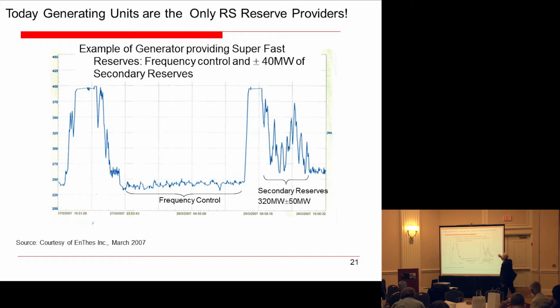Look at this generator, going up and down, providing 50 megawatts of regulation. However, not all 50 is required at once, so there's a swing of almost 100, with typically 80% used, going from minus 40 to plus 40. He does that maybe 7 or 8 times over an hour.